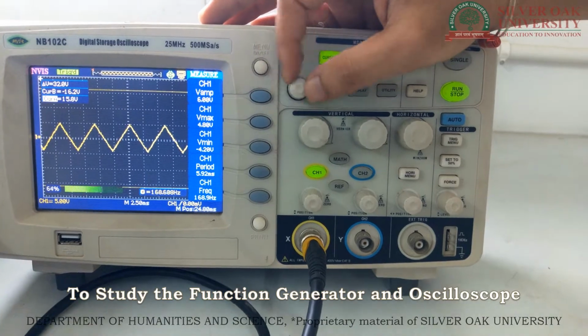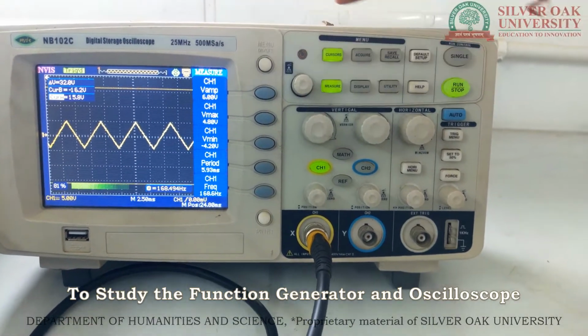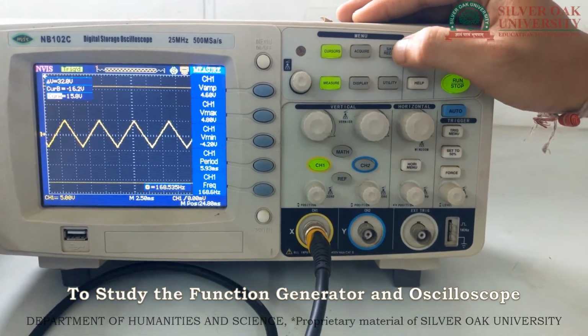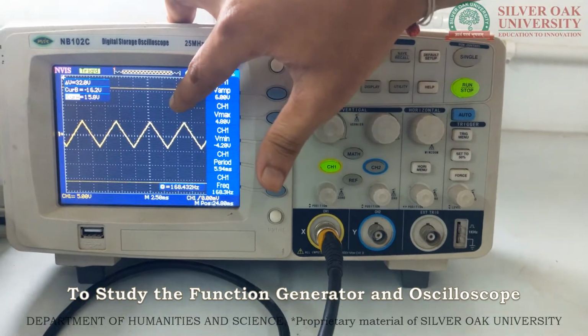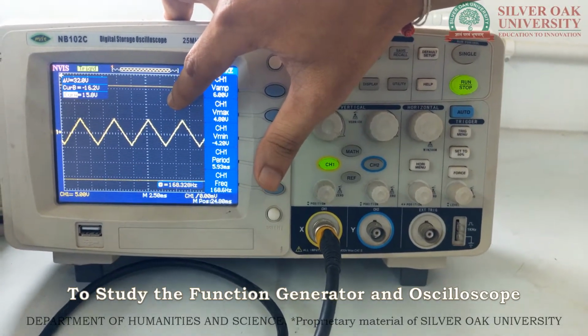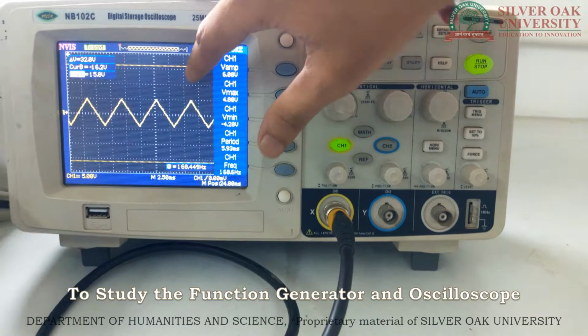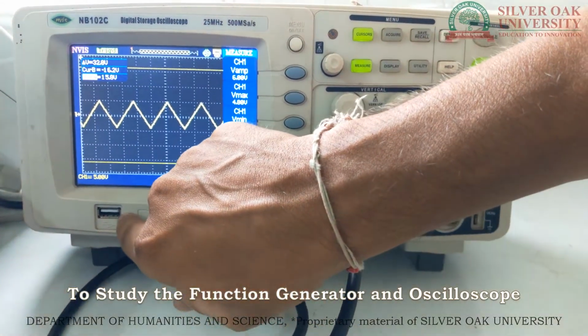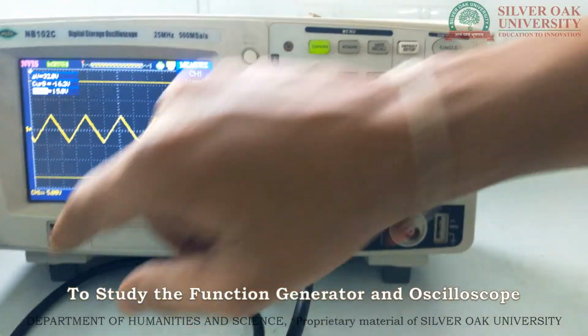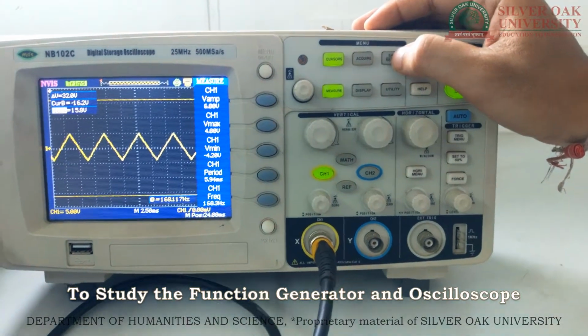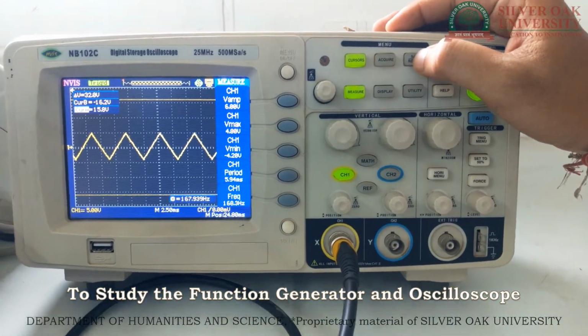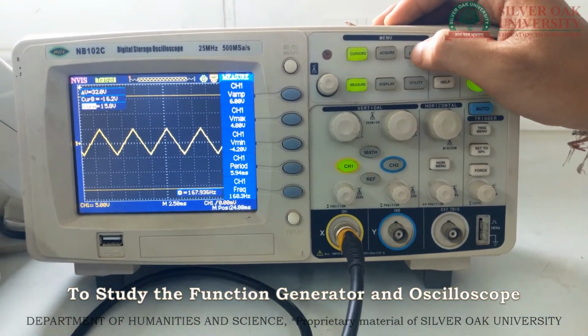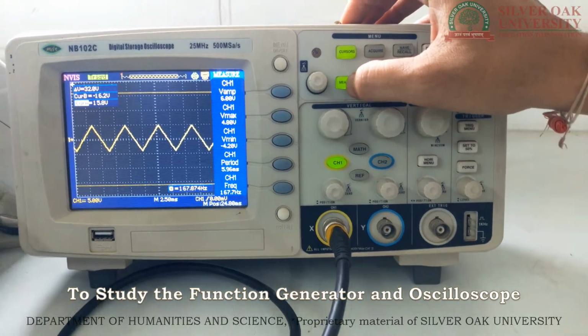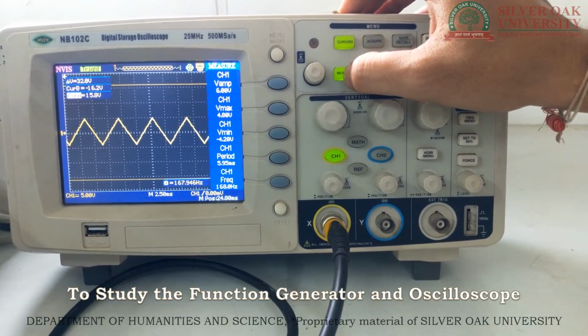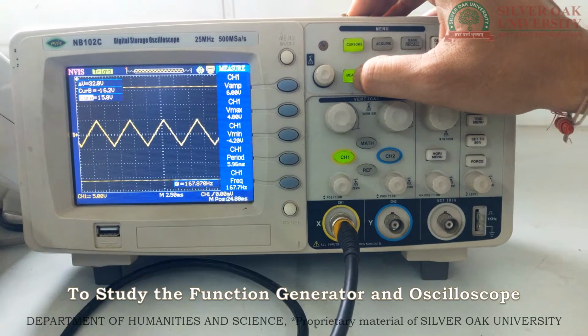Another option we have is save and recall. Now let us say I want to store this signal into my pen drive or other devices. Simply I need to insert my pen drive here, and after inserting, I will choose this option, save and recall. The waveform will get stored in that particular device. Another option is the measure. This button is basically used for taking the measurements of the signal.